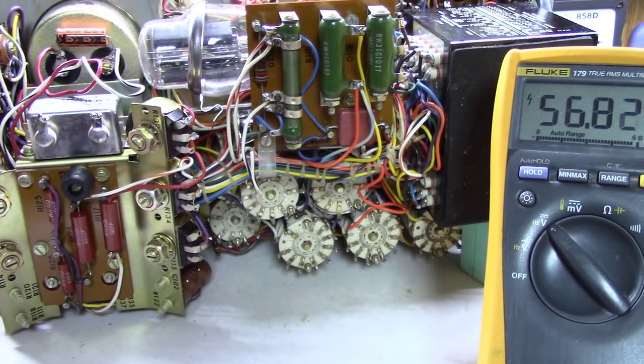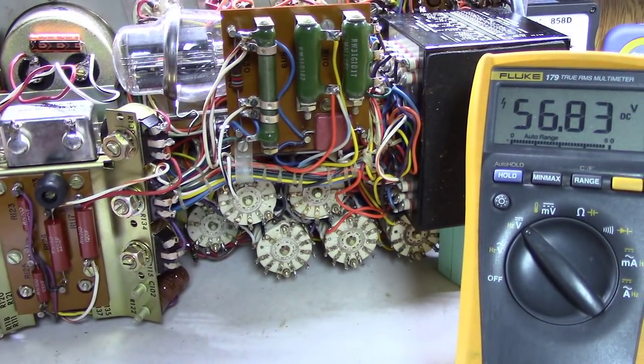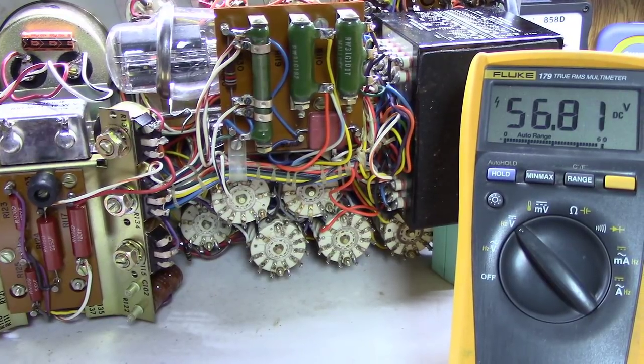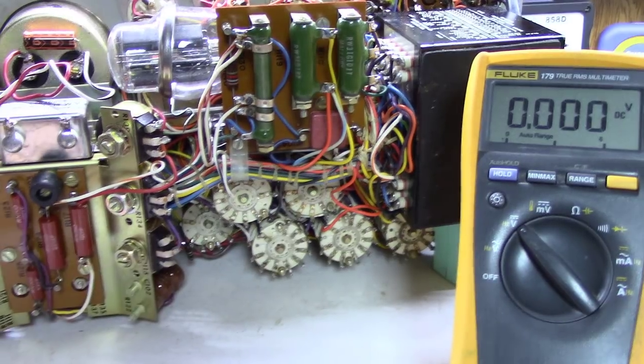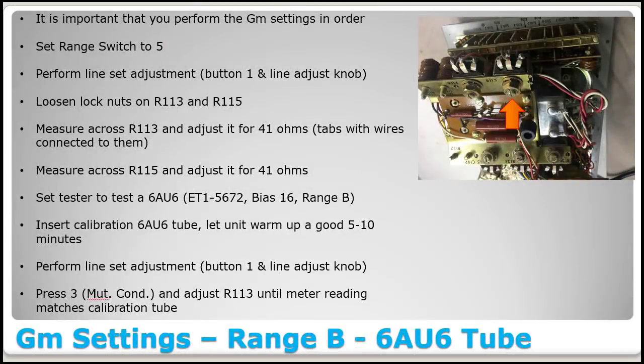Okay, one thing I will tell you is if you don't get these voltages fairly close in line, you will never get one of these things calibrated. So it's all about getting the screen and grid voltages. We've already done the line adjust voltage. Now we will move on to the actual calibration tubes and the settings around those that will all revolve around these potentiometers right here. Okay, it actually gets pretty easy from here and goes pretty fast from here.